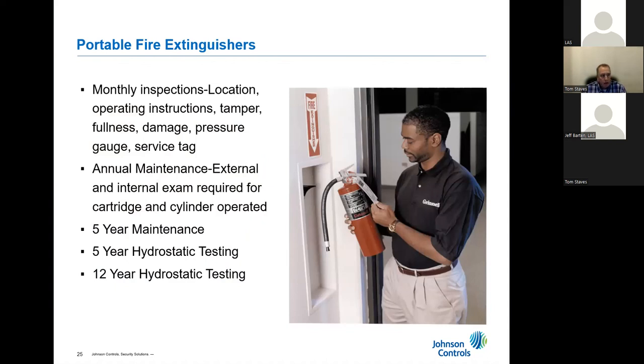And then you could see we also do the 5-year testing for maintenance, hydrostatic testing, and typically even after 12 years, depending on the size of the extinguisher, a lot of times it just gets to be cheaper to replace that and put in a new unit.